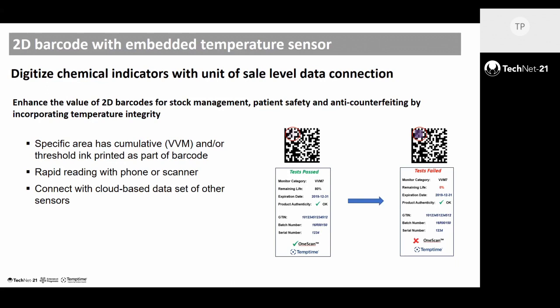Okay, thank you. Snehal Singh is asking, is there any independent study to prove the relation of VVM decay rate with antigen decay rate? This is Umit. Hello, do you hear me? Yes, we can hear you. Well, there are some early studies that show the correlation between VVM color change and the degradation of the vaccine. This was mainly done by NIBSC in the UK during the early implementation times of VVM with the oral polio vaccine.